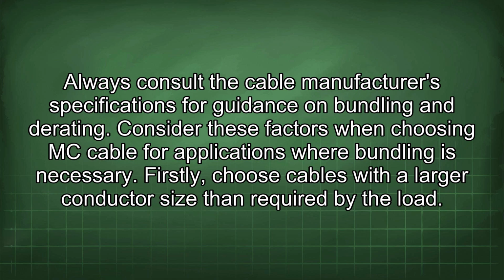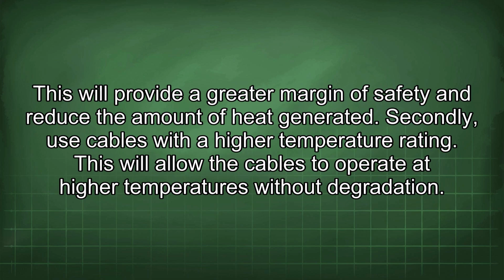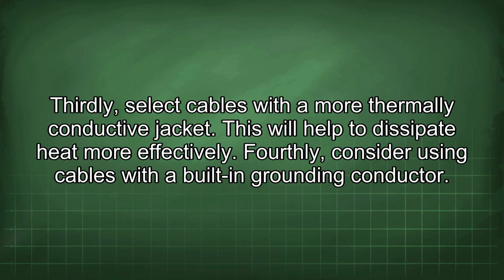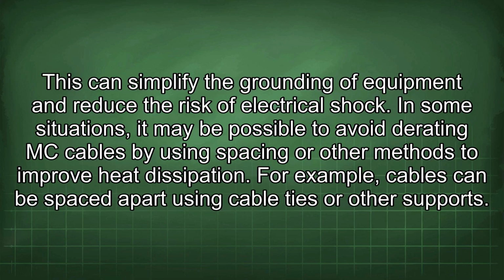Consider these factors when choosing MC cable for applications where bundling is necessary. Firstly, choose cables with a larger conductor size than required by the load. This will provide a greater margin of safety and reduce the amount of heat generated. Secondly, use cables with a higher temperature rating. This will allow the cables to operate at high temperatures without degradation. Thirdly, select cables with a more thermally conductive jacket. This will help to dissipate heat more effectively. Fourthly, consider using cables with a built-in grounding conductor. This can simplify the grounding of equipment and reduce the risk of electrical shock.